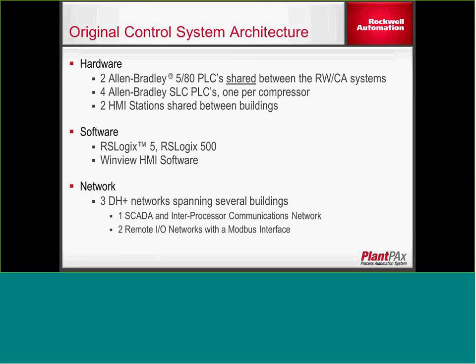The original control system architecture had two PLC-5 PLCs shared between the refrigerated water and compressed air systems. There were four Allen-Bradley SLC PLCs, one per compressor, and two HMI stations shared between three buildings — so there wasn't a lot of visibility with only one HMI per building. The software used was RSLogix 5 and 500, with the Winview HMI. The network consisted of three DH Plus networks spanning the three buildings: one for SCADA and inter-processor PLC-to-PLC communications, two for remote I/O networks, and a Modbus interface for the chillers.